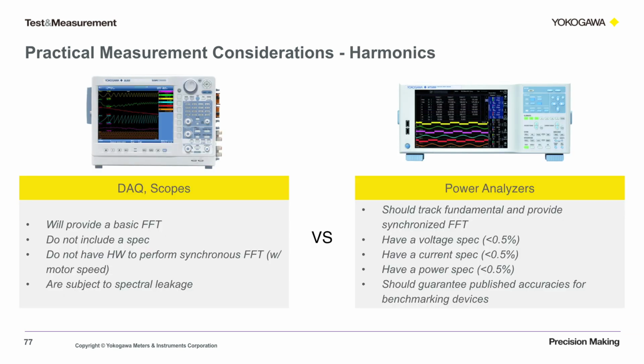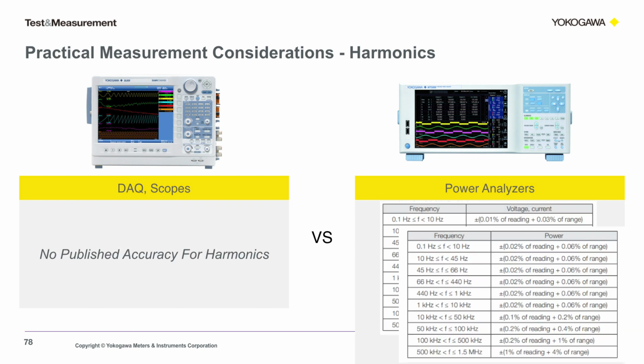The same argument of accuracy applies to harmonics. If you're using an instrument to provide harmonic details, the accuracy of the instrument also applies to those measurements. On the scope side, you'll have a basic FFT without a spec, and you'll be subject to spectral leakage. On the power analyzer side, you have a spec again for voltage, power, and current, and using a tracking PLL, you'll have a lot less spectral leakage. Most DAQ or oscilloscope products don't list specifications for harmonics at all. Power analyzers give the same level of detail up to the full frequency, as you can see here.